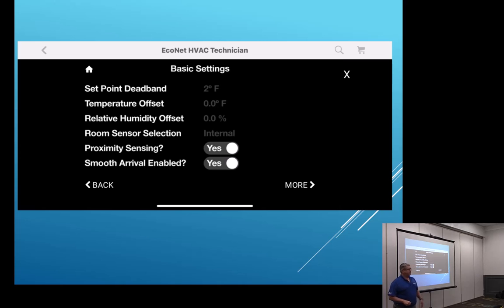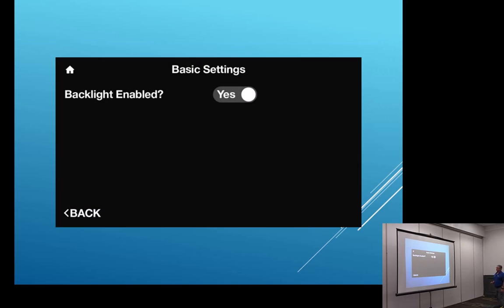Smooth arrival. Do we know what smooth arrival is? If you have a schedule set to bring it from 78 to 74 degrees at 4 o'clock, smooth arrival knows what the temperature is outside and what the temperature is inside. So it's going to come on at 3:15, so when you walk through the door at 4 o'clock, it's 74 degrees. If you don't want that, you can click it off and it'll just start coming down at 4 o'clock to 74 degrees. So it might take a half hour to get there, but that's what smooth arrival is.